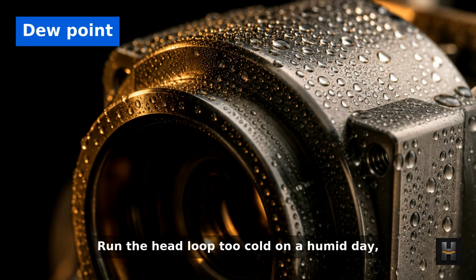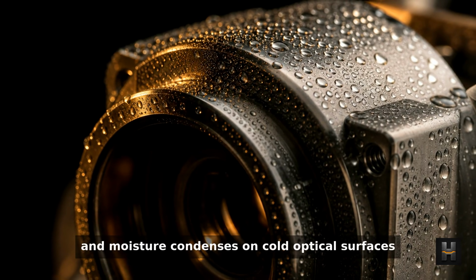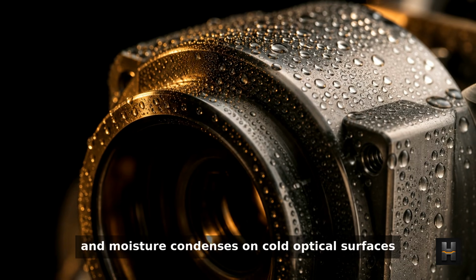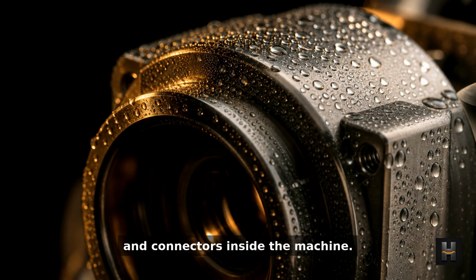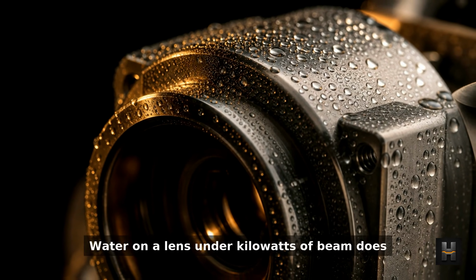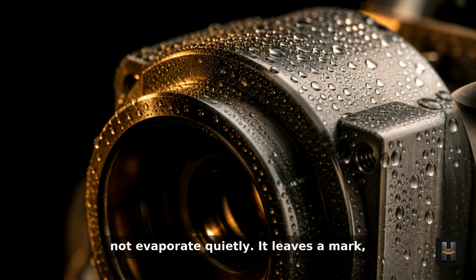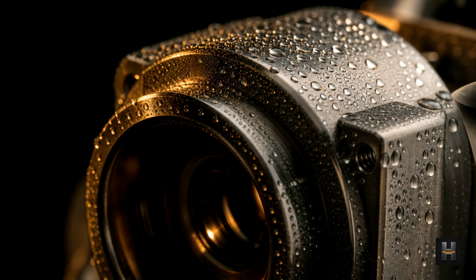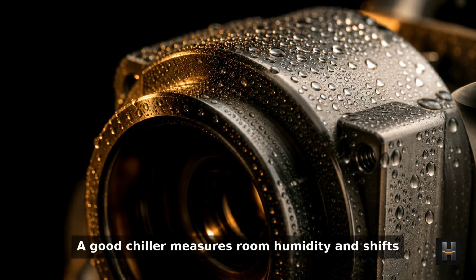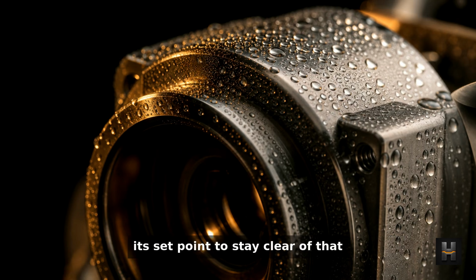Run the head loop too cold on a humid day and moisture condenses on cold optical surfaces and connectors inside the machine. Water on a lens under kilowatts of beam does not evaporate quietly. It leaves a mark, and then the mark absorbs. A good chiller measures room humidity and shifts its set point to stay clear of that.